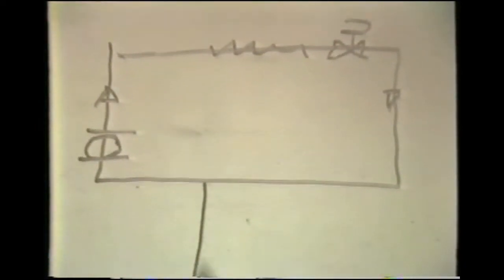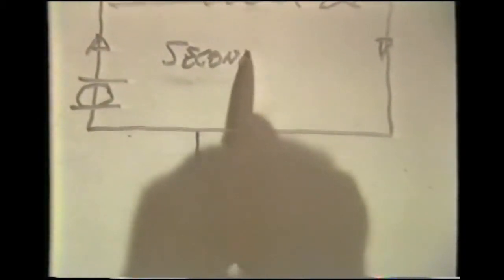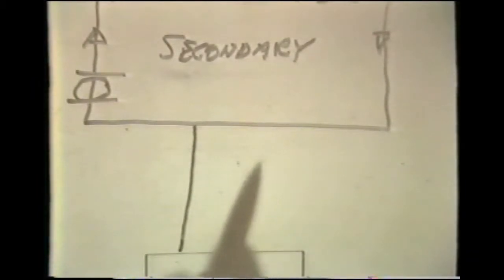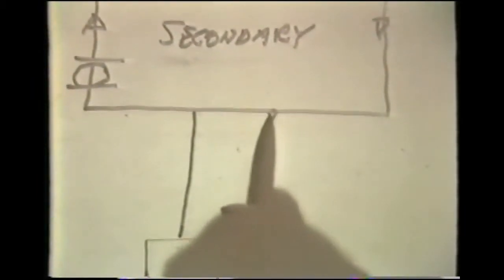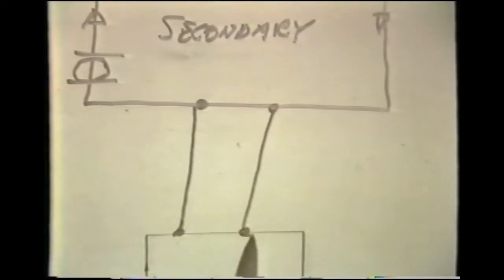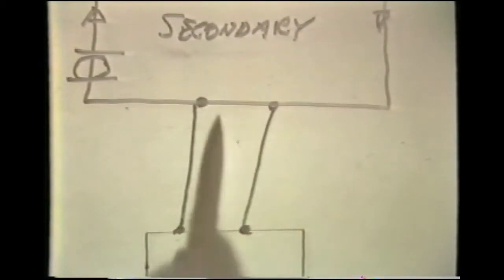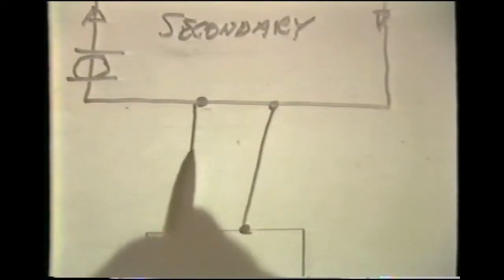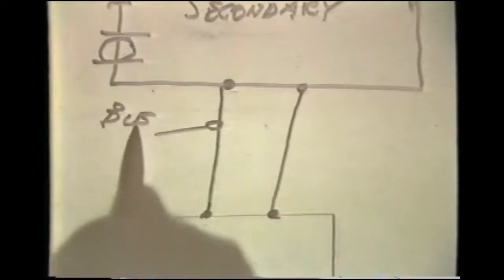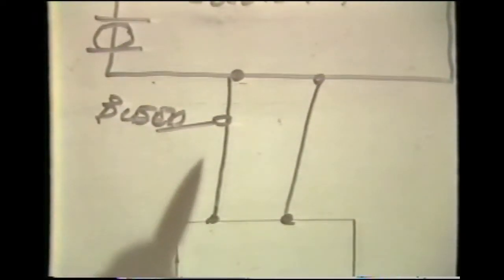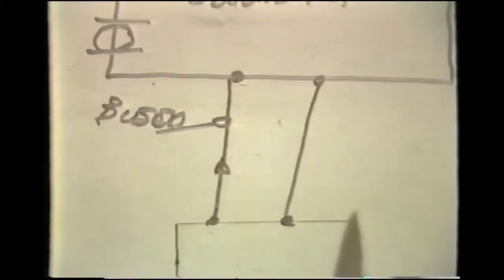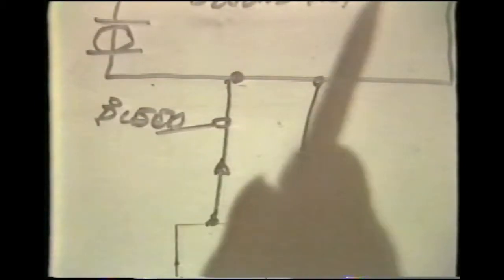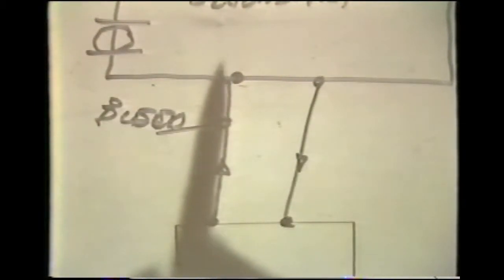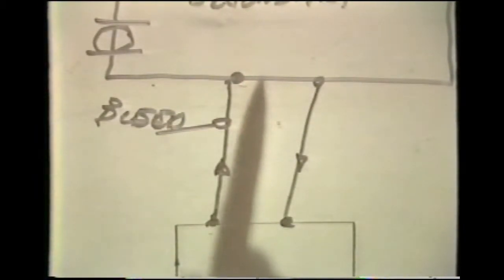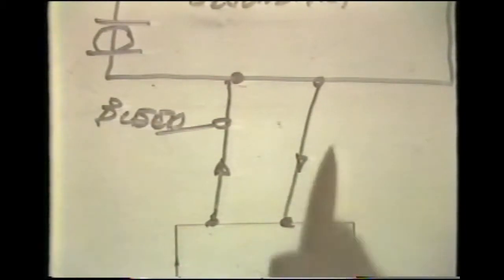Now we'll connect that from the secondary circuit to the primary circuit by two bleed lines. In this case, each bleed line being relatively close together so as to not cause any pressure drop in the bleed lines themselves. Now these bleed lines will bleed, in this case this being intended for hot water application, the necessary flow rate into that circuit and out of that circuit to maintain the required temperatures for the secondary system, whether this be for comfort heating and or whether it be for a storage tank application.